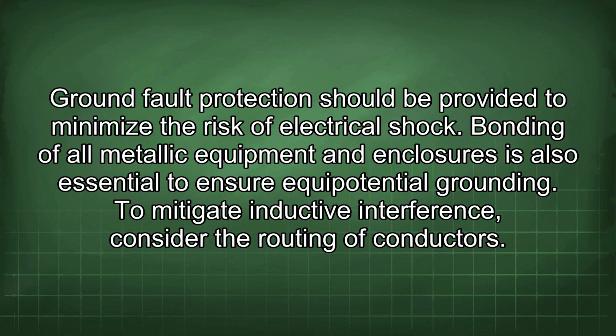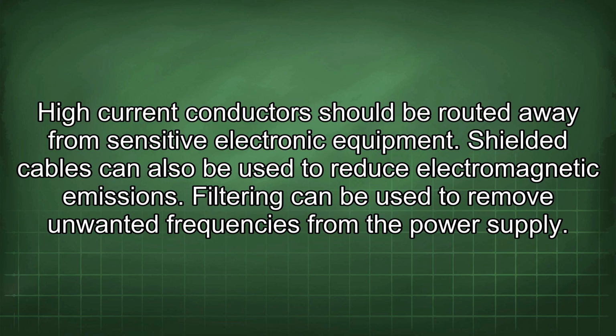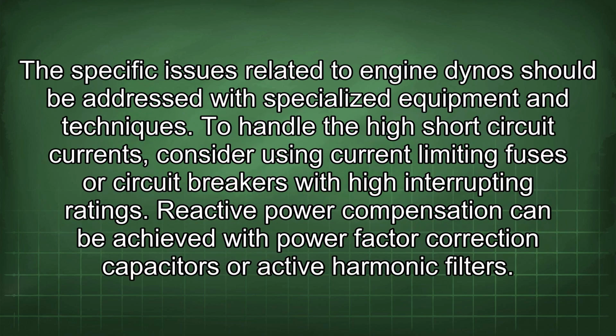Bonding of all metallic equipment and enclosures is also essential to ensure equipotential grounding. To mitigate inductive interference, consider the routing of conductors. High current conductors should be routed away from sensitive electronic equipment. Shielded cables can also be used to reduce electromagnetic emissions. Filtering can be used to remove unwanted frequencies from the power supply. The specific issues related to engine dynos should be addressed with specialized equipment and techniques. To handle the high short-circuit currents, consider using current-limiting fuses or circuit breakers with high interrupting ratings. Reactive power compensation can be achieved with power factor correction capacitors or active harmonic filters.